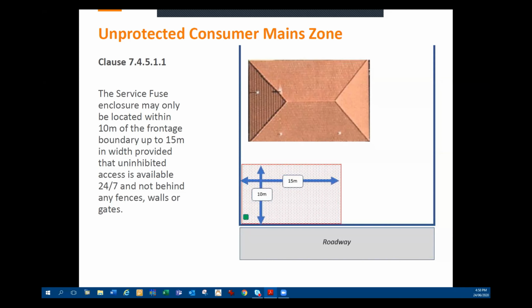So we're just trying to reduce the distance for unprotected mains for where it goes into a service fuse enclosure to be changed to protected mains. So the service fuse enclosure basically needs to be accessible 24/7 and not behind any walls or fences or gates, etc.